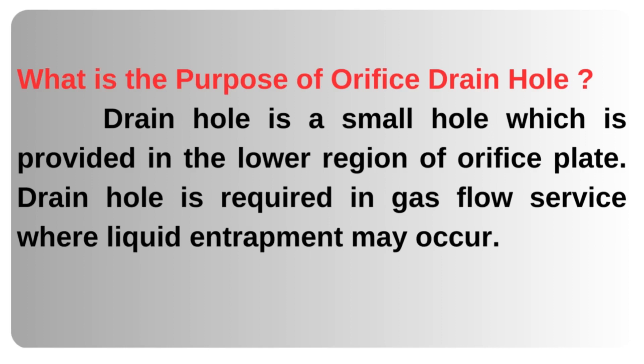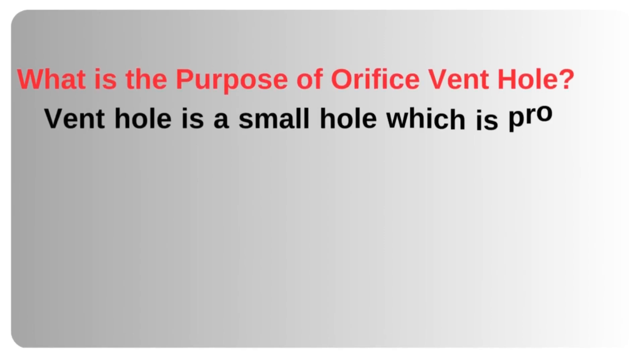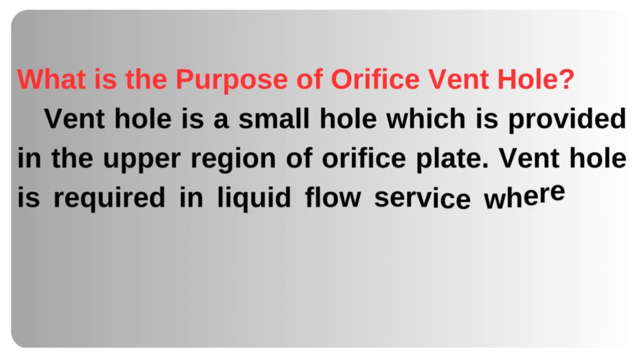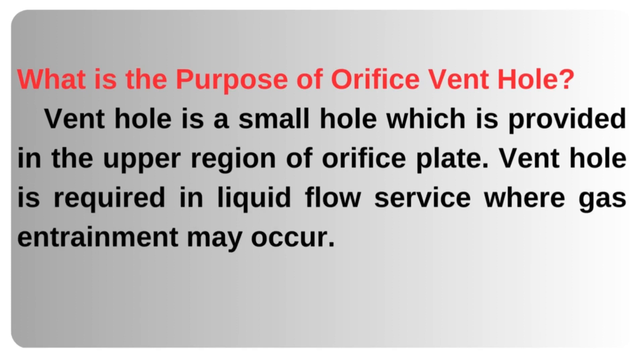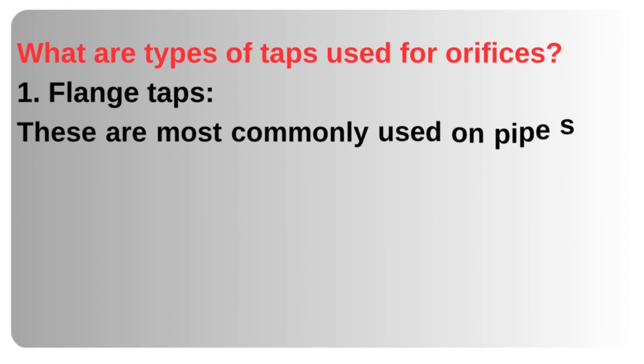The drain hole is required in gas flow service where liquid entrapment may occur. What is the purpose of the orifice vent hole? The vent hole is a small hole provided in the upper region of the orifice plate. The vent hole is required in liquid flow service where gas entrapment may occur.